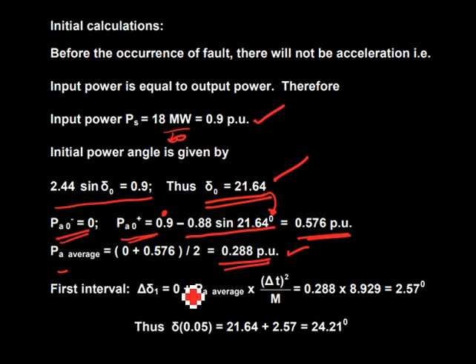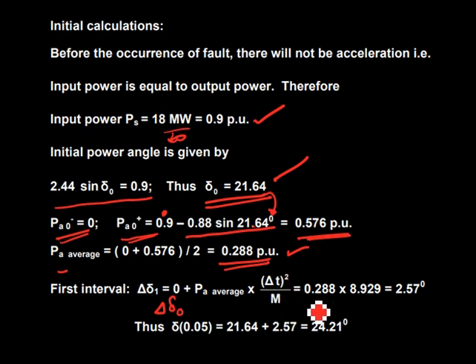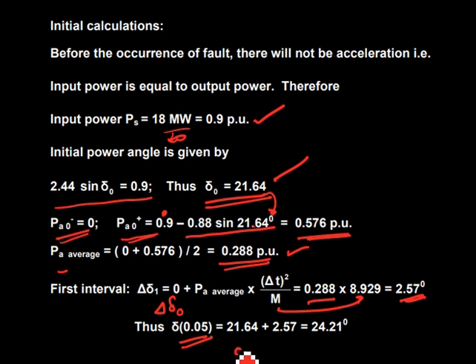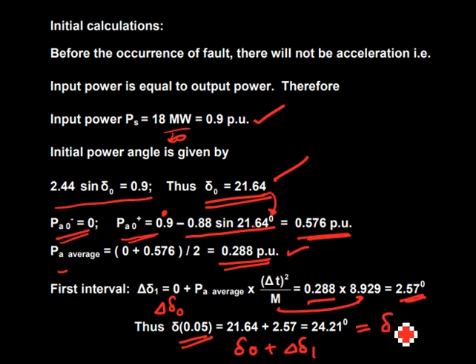The first change in delta: delta-delta(1) = delta-delta(0) + Pa_average × (delta-t²/M) = 0 + 0.288 × 8.929 = 2.57 degrees. Therefore delta at the first interval: delta(1) = delta(0) + delta-delta(1) = 21.64 + 2.57 = 24.21 degrees at t = 0.05 seconds. This new value of 24.21 degrees becomes the starting point for the next set of calculations.